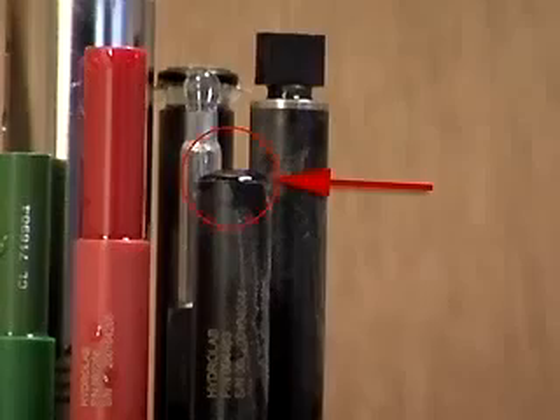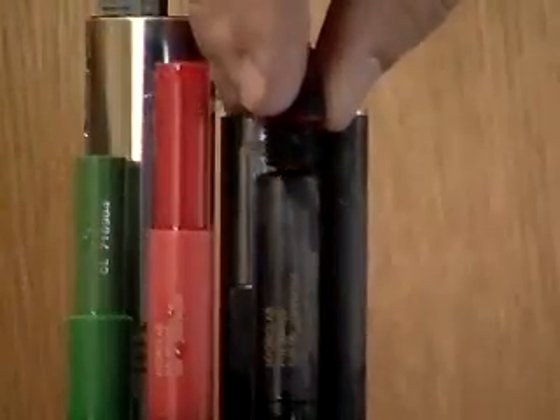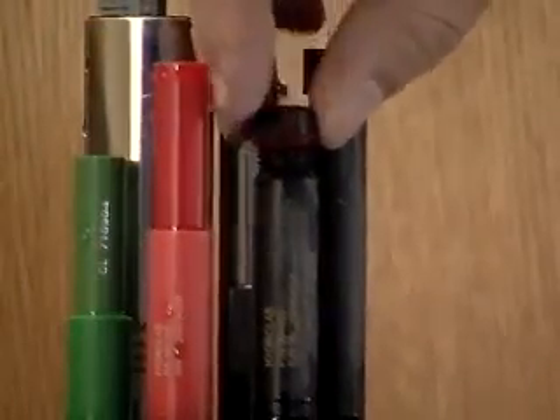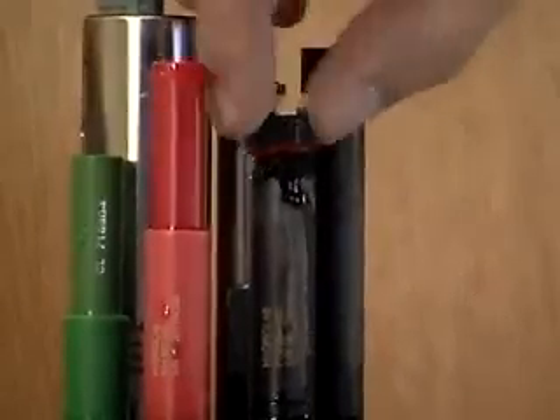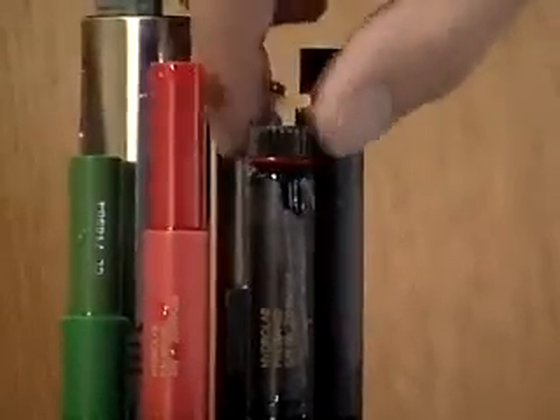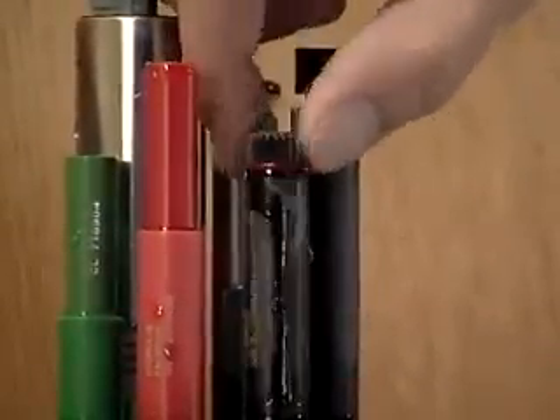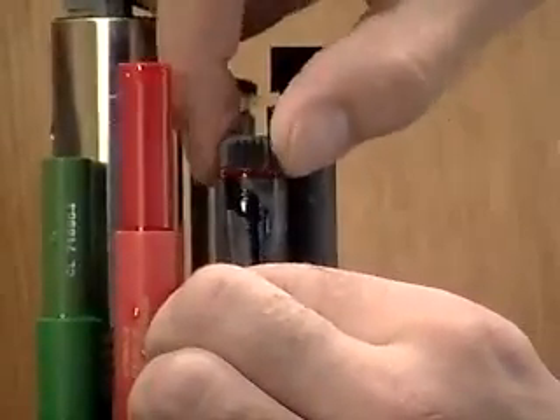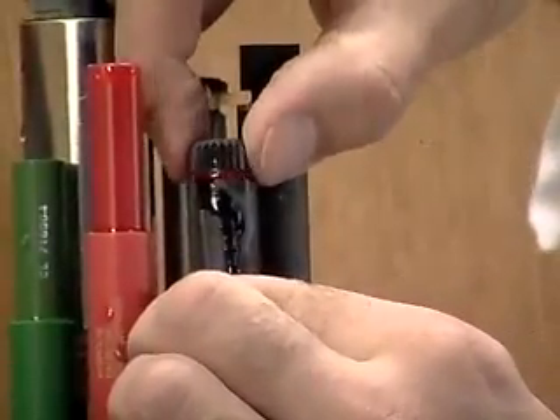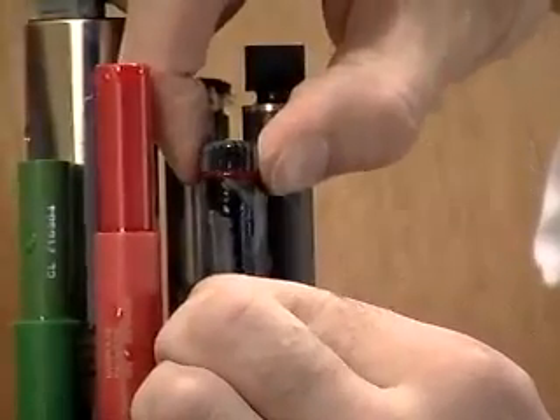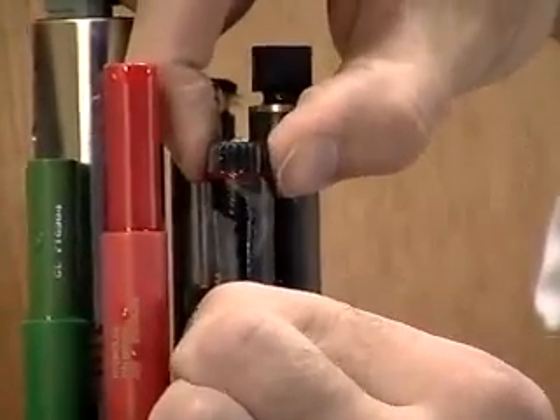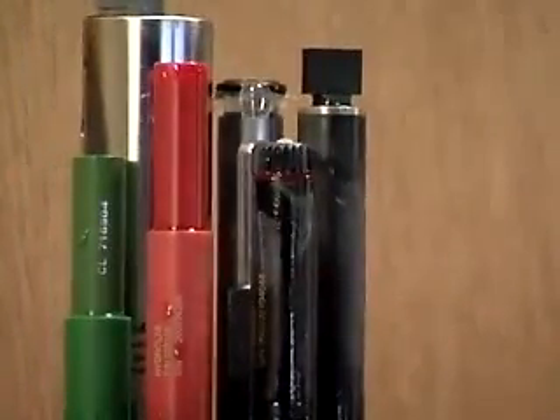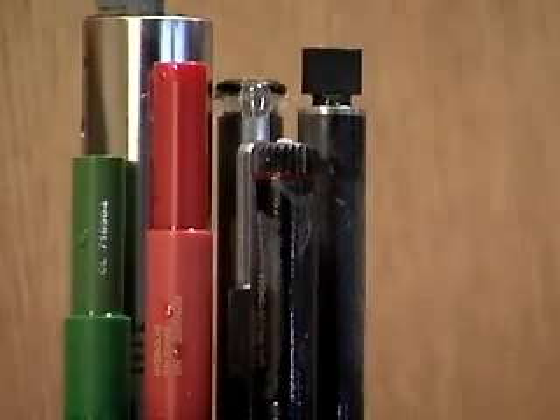Gently place the new junction onto the top of the reference tube so that no air remains inside, and turn it clockwise until the O-ring is sealed tightly. As you tighten, you will see a small amount of electrolyte and possibly bubbles being forced out of the junction. This is the air being purged from inside the junction. If this purging effect does not occur, the junction may be clogged and must be replaced. The pH sensor is now ready to be calibrated.